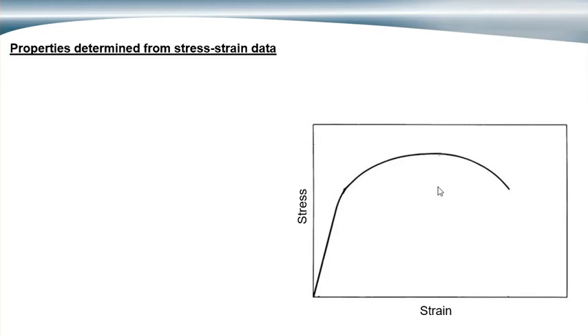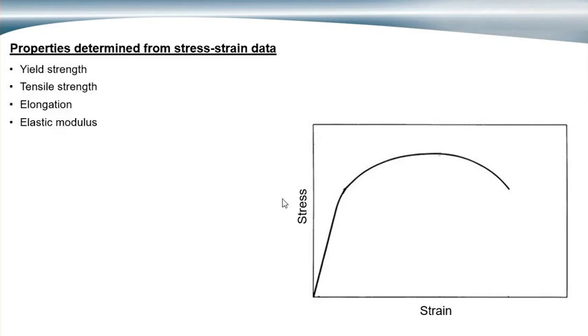There are a number of properties determined from the data obtained. The force data is used to calculate the stress, and the deformation data is used to calculate the strain. From that, we can plot stress versus strain and determine the material's yield strength, tensile strength, elongation, and elastic modulus.